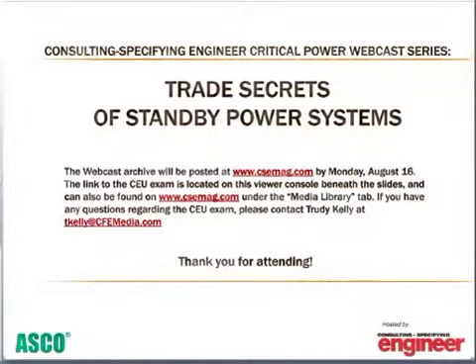Got it. Quick question to you, Ken. What should the minimum room temperature be? This is from Dan Lieber from AECOM. We generally try to have the room temperature somewhere in the 60-degree range as a minimum. As you get colder, the oil, of course, thickens up, and it's going to slow the engine start time down. So you want the delay to be as small as possible due to the temperature issues.